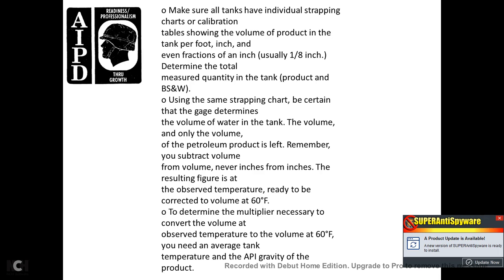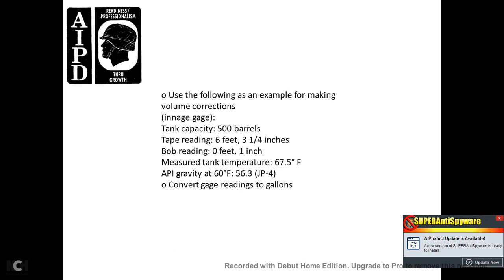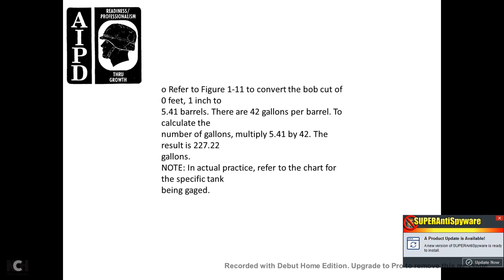To determine the multiplier needed to convert volume at the observed temperature to 60 degrees Fahrenheit, you need the average tank temperature and the API gravity of the product. For example: innage gauge, tank capacity 500 barrels; tape reading 6 feet 3 and one-quarter inches; bob reading 1 inch; measured tank temperature 67.5 degrees; API gravity at 60 degrees Fahrenheit: 56.3 (JP fuel). Refer to Figure 1-11. Convert the bob cut of 0 feet 1 inch to 5.41 barrels. There are 42 gallons per barrel; multiplying 5.41 times 42 gives 227.22 gallons. In actual practice, refer to the chart for the specific tank being gauged.